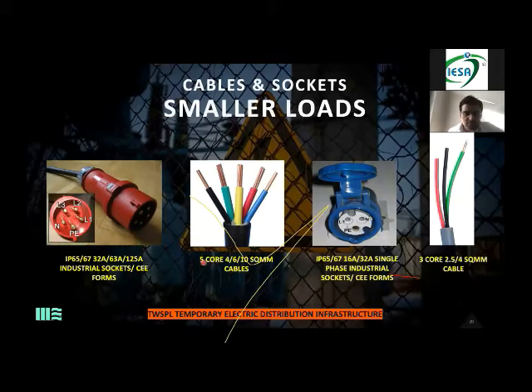So over here, you see 5 core, 4, 6 and 10. Again, cables come in square mm, and certain square mm wires are meant for certain kinds of sockets. Maybe a 5 core 4 square mm wire is meant for a 32 amp socket, which means 10 kilowatts. If I have to give a load of 10 kilowatts to an exhibition stall or exhibitor, we use a 5 core 4 square mm wire and this socket, and at the end point we give an MCB, which I'm going to talk about.